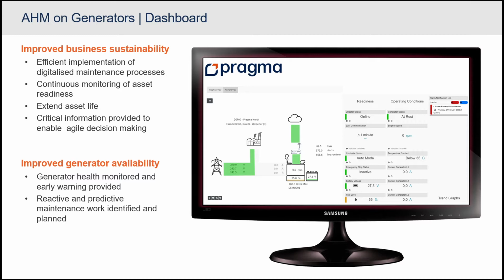We've tried to customize it to make it easy to see the health of your assets, breaking it into two sections: readiness and operating conditions. If everything is green under readiness, the generator should be able to start — communication should be online, the generator should be in auto mode, the emergency stop button shouldn't be pressed in, the battery should be charged, and there should be enough fuel. If all of that is green, the generator should start.